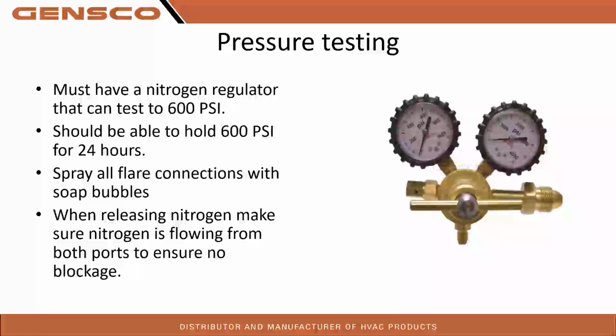Mitsubishi's requirement is it should be able to hold a 600 PSI pressure test for at least 24 hours. So I'm sure most of us, we don't have 24 hours bid time on our jobs in order to do that pressure test. I get it. So we try to do the best we can. What I recommend for you guys is, once you get to the job site, get your unit set and get that system on pressure test as quickly as you can. That way you can hold it on pressure as long as you can while you're doing your wiring, condensate drains, all that kind of stuff.